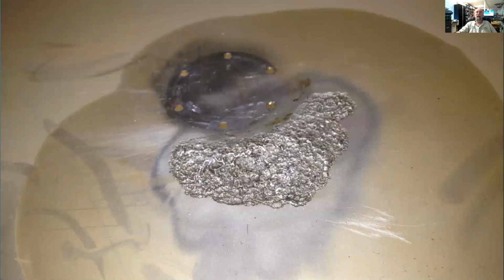That's a bit of slag. What you see there is where one of the fixed vacuum capacitors was bolted to the shield, the piece of metal you're looking at, and the center conductor. At some time there was a major arc over, and you can see it created a bit of slag. This is actually on the inside; we first spotted it on the outside, where you can see this bubble of aluminum sticking out of the enclosure.